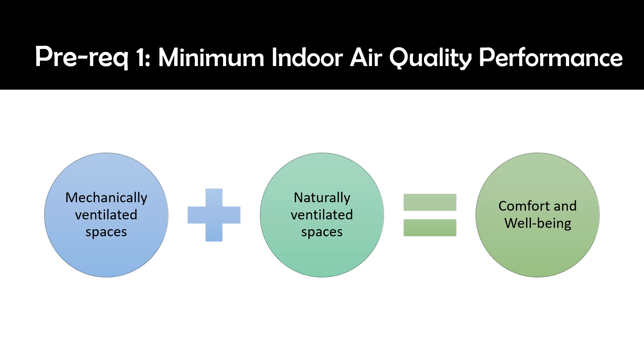The requirements for mechanically ventilated spaces is to meet the requirements of ASHRAE 62.1 — remember, 62-1 is for ventilation — and provide outdoor air monitors for all larger mechanical ventilation systems. For naturally ventilated spaces, meet one of the three ASHRAE ventilation requirements listed in LEED. And for all spaces, measure the exhaust air flow, indicate natural ventilation openings with an alarm when closed during occupied hours, and monitor CO2 concentrations in each thermal zone.